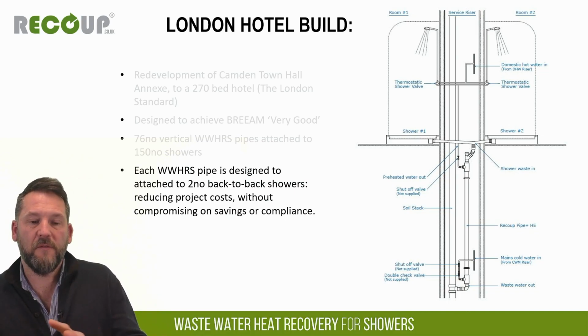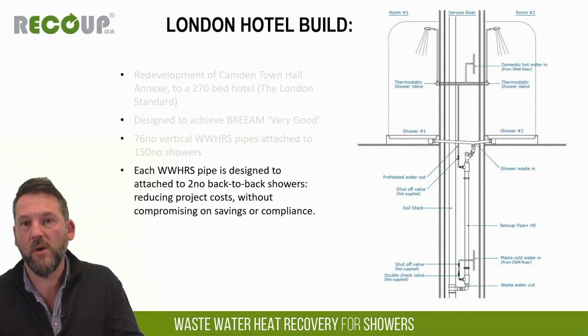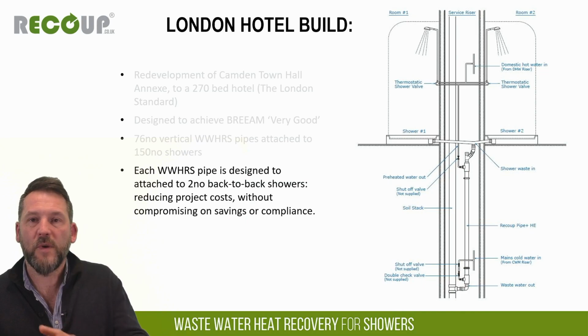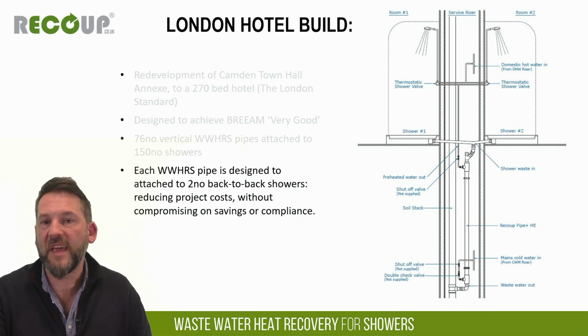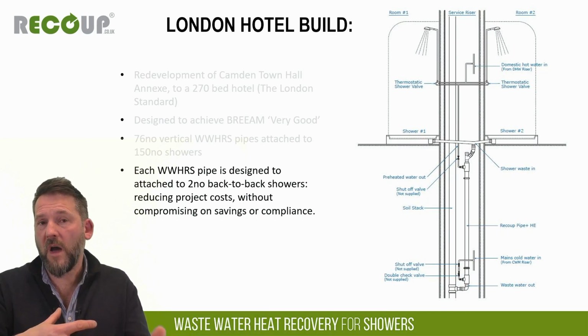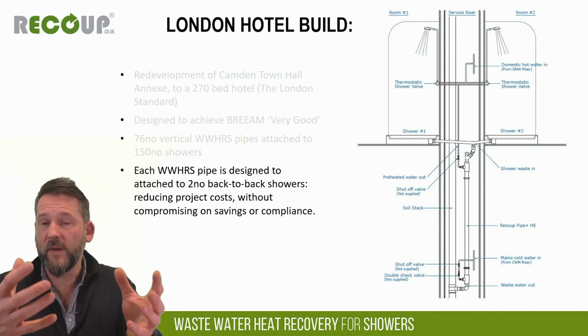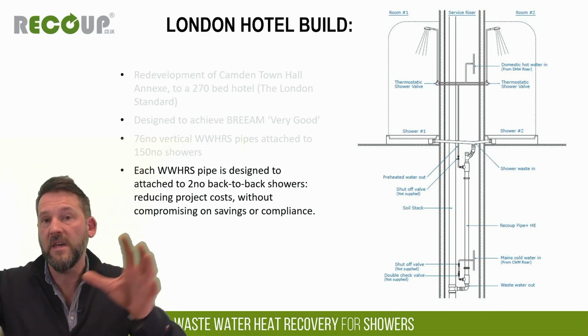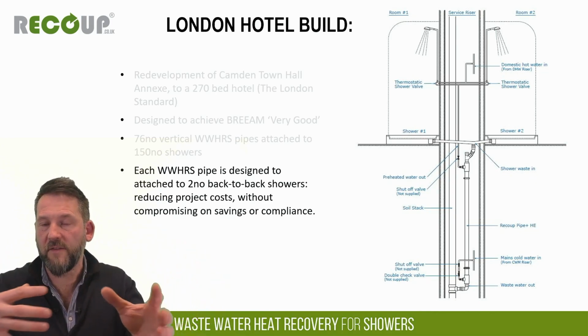We have full Legionella guidance and a Legionella report from Legionella Control, who are risk assessors for Legionella, so we have all that paperwork behind this. While there are some more nuanced elements, the main two parts are that this unit isn't in an area of high ambient heat, so it's allowed to cool down as quickly as possible, and it doesn't have a heat source next to it. So if you've got heating and cooling ducting going through, that might need to be considered to be suitably far away from the unit if it's in a riser.